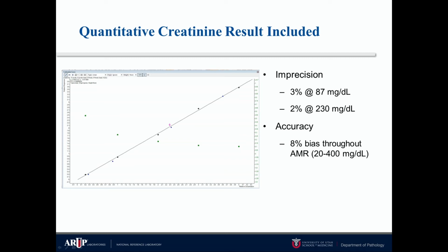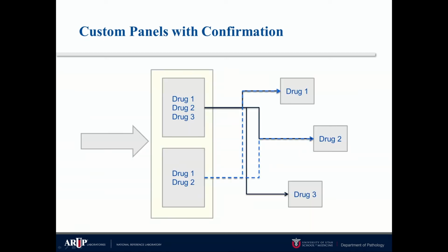And it's interesting to see how harmonized a lot of the creatinine assays are, but it doesn't necessarily mean that they are perfectly accurate. And so we are continuing to look at that 8% bias, even though certainly not unacceptable, something we are interested in looking at a bit closer.